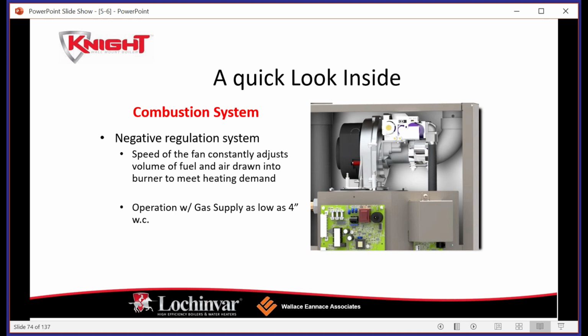At the back of the cabinet, you can see here that there is the fresh air intake, which is getting pulled into the fan. You're creating a Venturi effect, and the gas valve is going to snap open. The fuel is going to flow through the gas valve into the casting of the fan body, and it's going to create an air-fuel mixture, okay? As the fan speeds up and slows down, it's going to be creating a higher or lower air-fuel mixture, and it's going to allow the boiler to fire up and down. It's going to modulate like we discussed before, and that's what's going to get us our turndown.